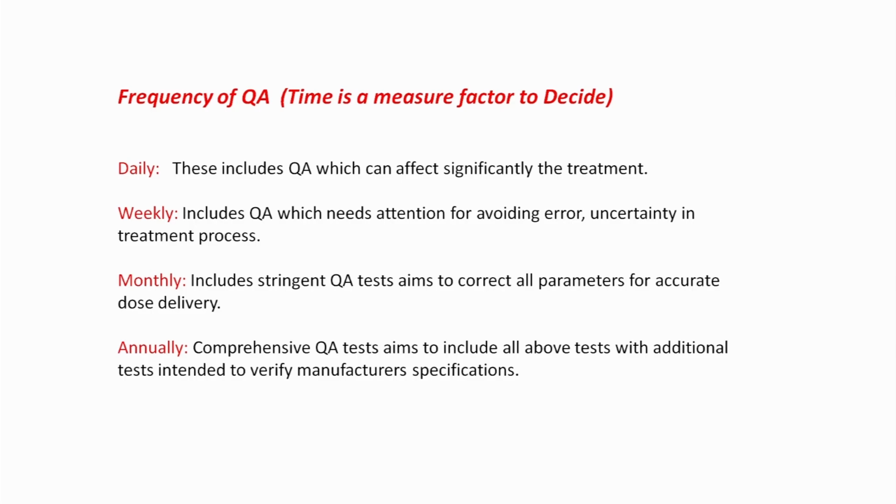First is the daily quality assurance. These quality assurance tests include those which can significantly affect the treatment. It is a quality assurance which needs to be performed daily, so that you can verify the daily performance of your machine, the linear accelerator.